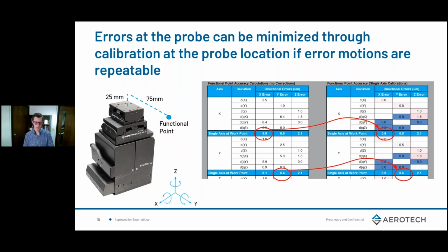And that's what you're seeing here. You'll see on the left-hand side, the uncalibrated stage with plus or minus 7 microns of accuracy over the full travel. And on the right-hand side, the calibrated stage with an order of magnitude smaller, plus or minus 600 nanometers of accuracy at the probe tip. So we can account for all of or most of the moment arm error due to your probe tip offset to the optical encoder just by calibrating at that point. So at Aerotech, we're going to ask you where is your point of interest and what is your payload for this reason.